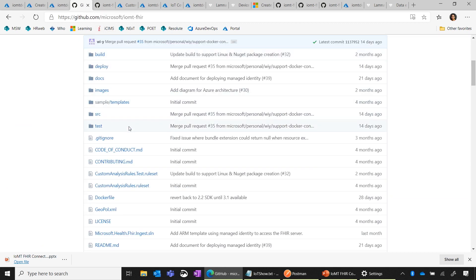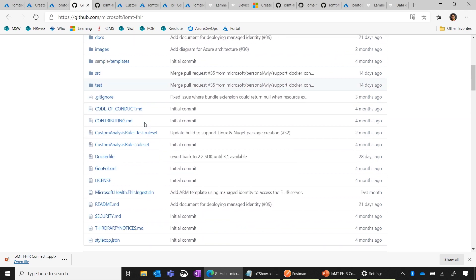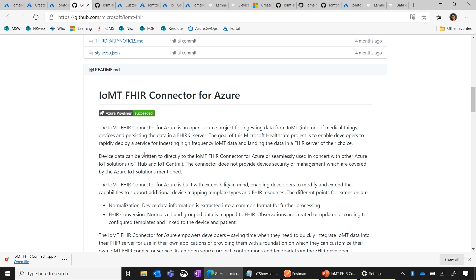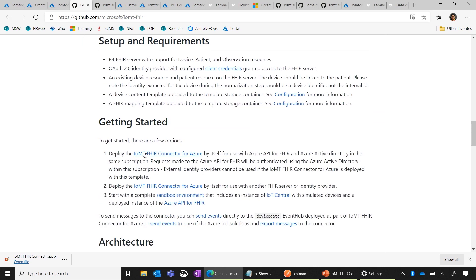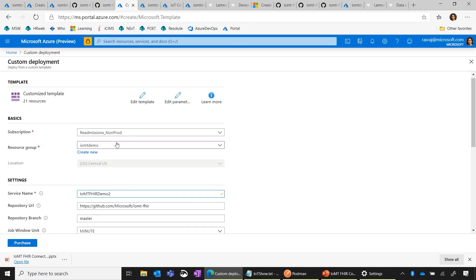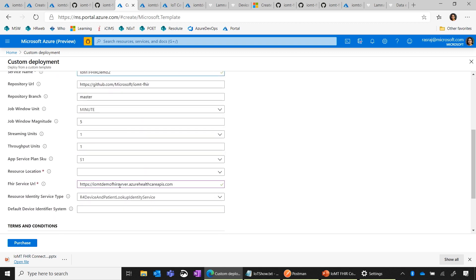In the second step, I go to GitHub. This is the IOMT FHIR GitHub repository — we'll have a short link at the end of the presentation. Here we have rich documentation about the architecture, how to use it, and how to debug it. For easy deployment, you just go to Getting Started and click Deploy to Azure. When you deploy to Azure, it brings you to a basic configuration screen where you can choose the resource group and put in the service name. The important thing is to use your FHIR server URL — just the basic URL without the slash metadata. So the IOMT connector is now deployed.